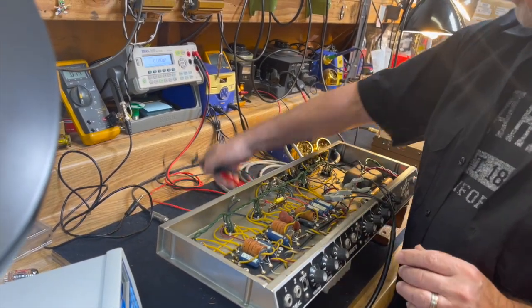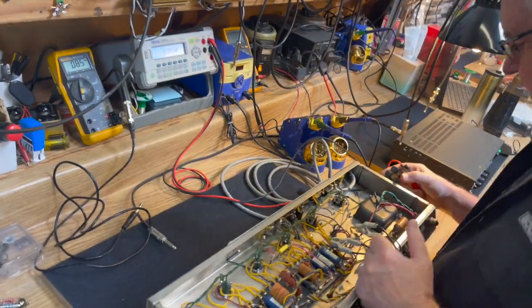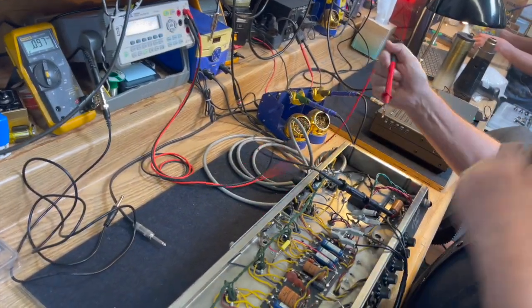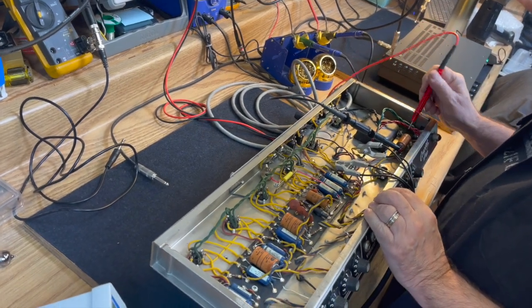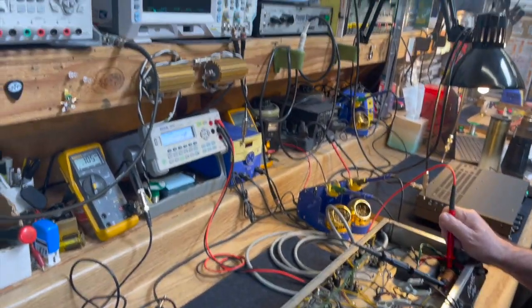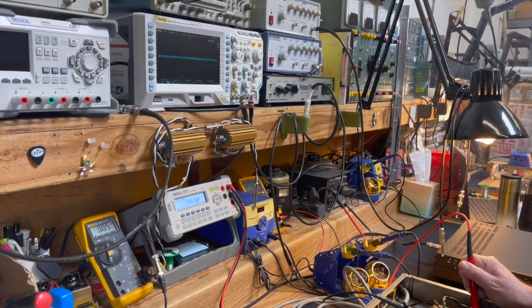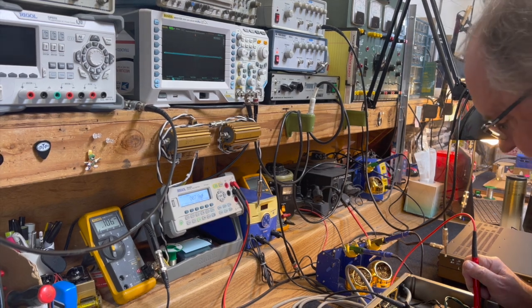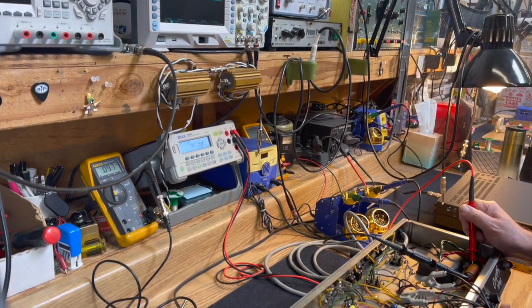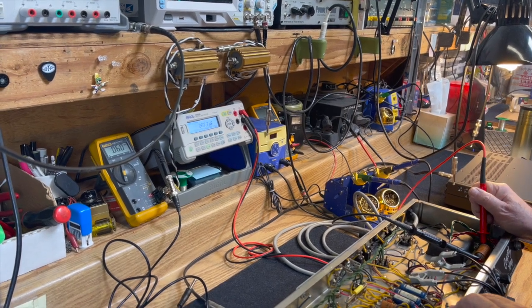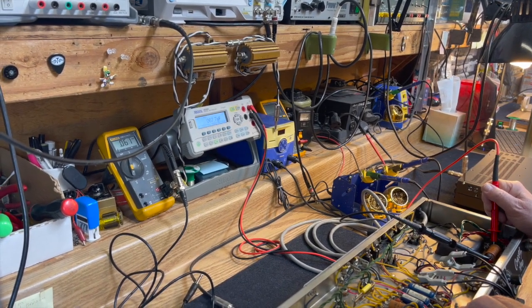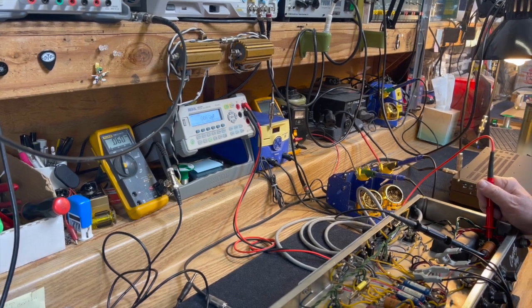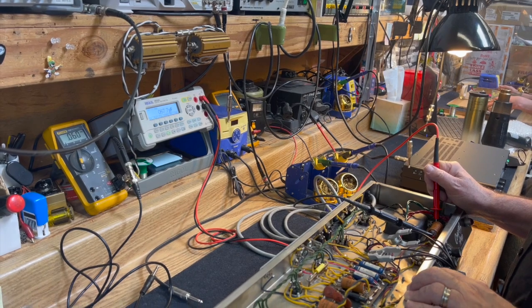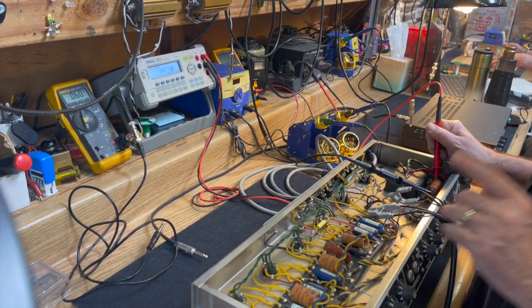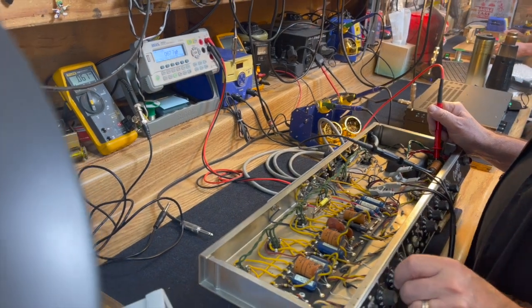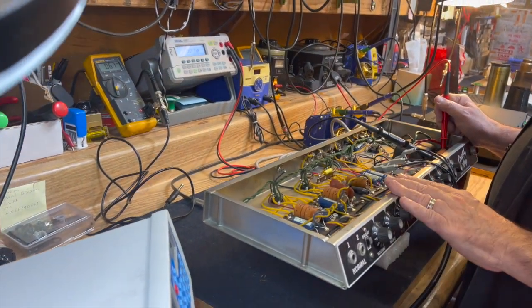Now, just for giggles, we're going to put the capacitor tester mode of the digital voltmeter across the same capacitor, and we're going to get 66 mics. Now, why would we get 66 mics? Besides the fact that they check things differently, it also could be that the digital voltmeter doesn't do as good of a job of testing the capacitors in circuit as the LCR meter does.